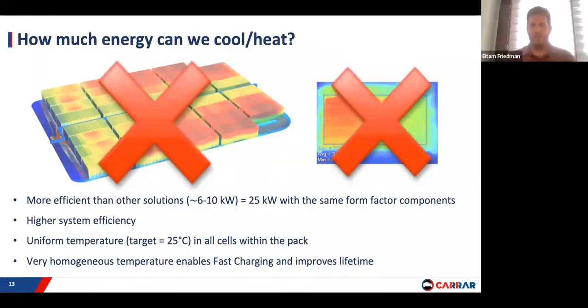We also tested keeping the batteries at 25 degrees, so we won't see temperature increase regardless of the C-rate. 25 kilowatts of heat from the battery pack correlates to very high C-rates, above 3, 4, or 5C - meaning we're now enabling ultra-fast charging.